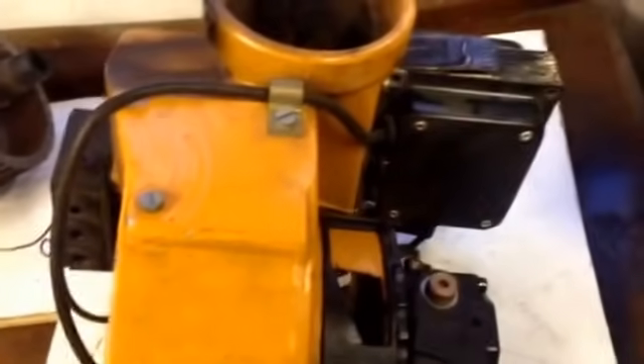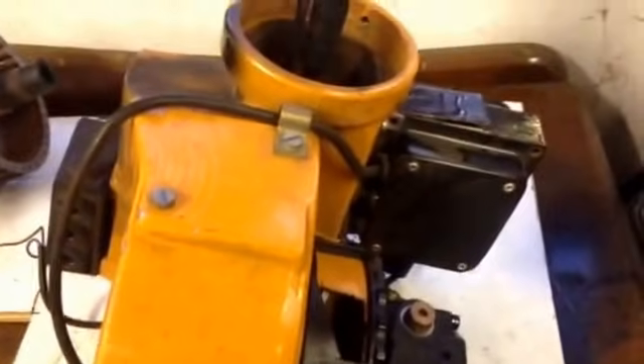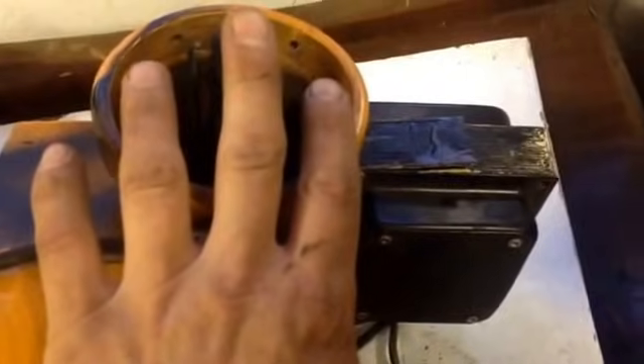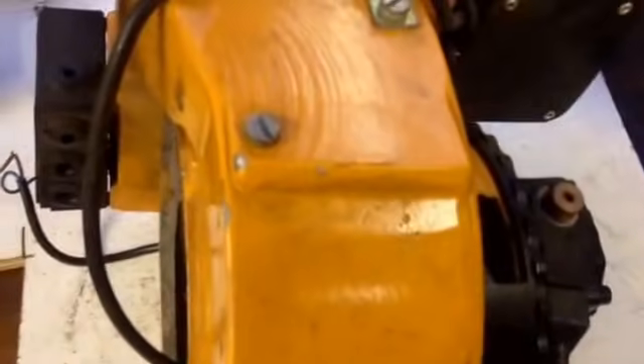Assuming that you hear the blow, and you can actually hear it blowing air through - if you then don't hear the spark, you know that what you've got is a spark failure. If you hear the spark and then you don't hear any ignition at all, you know you've got no fuel coming through. If you hear it blow, spark, ignite, continue to spark, and then lock out, you know what it's done is gone through its whole process but not been able to see that there is a flame.